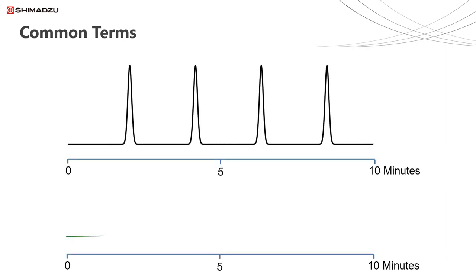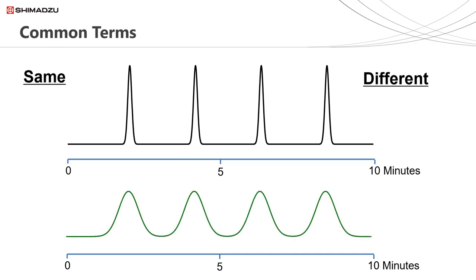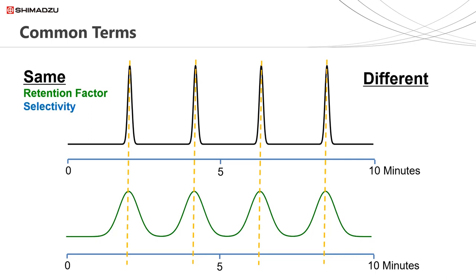I now want to introduce a number of terms and concepts which should be understood to continue building your knowledge in HPLC. The two example chromatograms on the slide show a number of similarities as well as differences. What is the same between these two chromatograms is the retention time and therefore retention factor of each of the four peaks. We can also say that the selectivity is the same — each peak elutes in the same order. What is different is the peak width, measured here at half the peak height. Because the width of these two peaks is different but the retention time is the same, we can also say that the peak efficiency is different. Lastly is resolution, which is a measure of how well two peaks are clearly separated — this is also different between these two chromatograms.